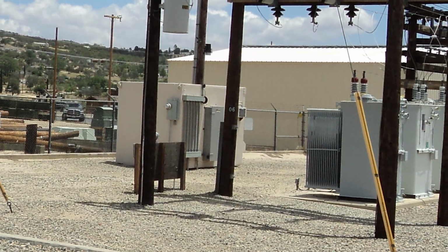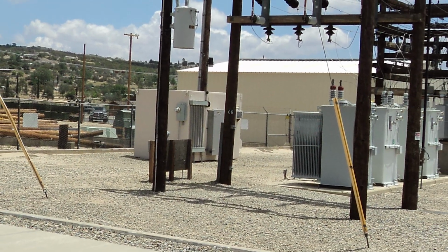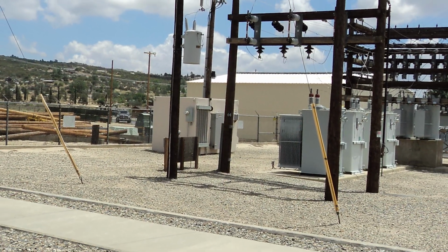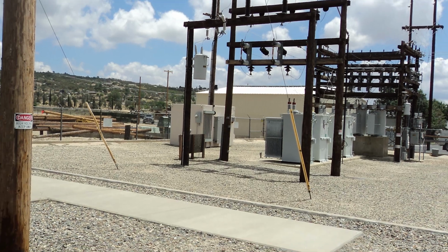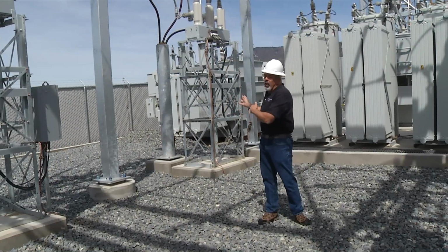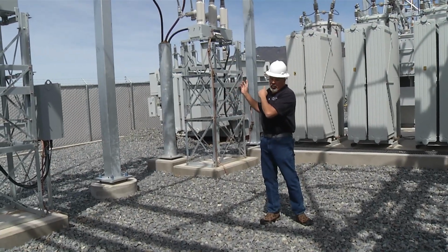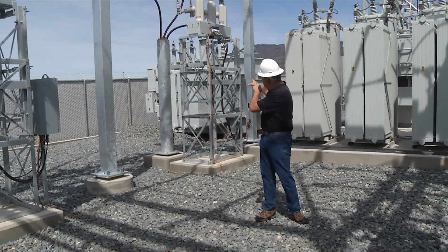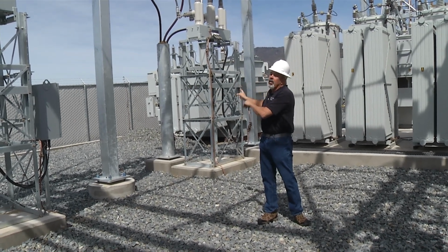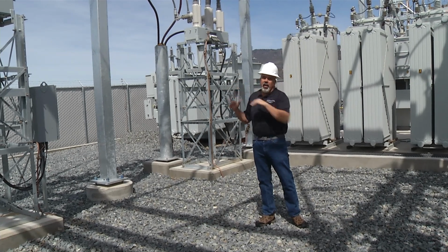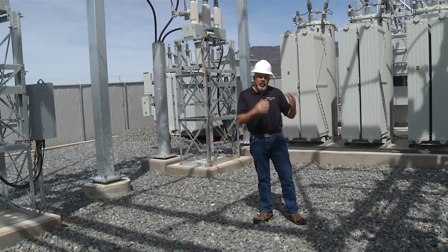Also, in order to keep the power flowing during construction, a temporary substation, very basic in design, had to be built. We had to build a bypass, or what we call a shoofly, to use this transformer, which we're going to be lifting out of here, and bypass the entire existing substation so it could be demolished and the new structure built.